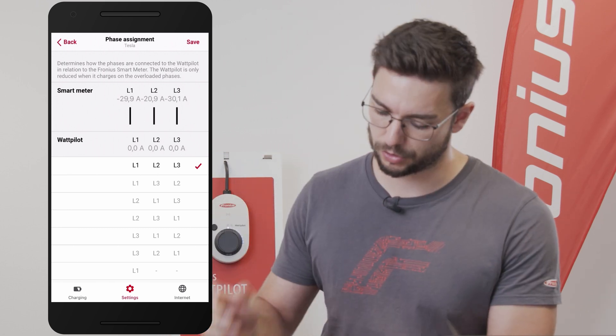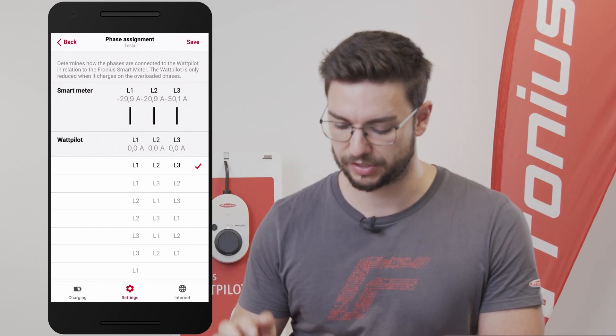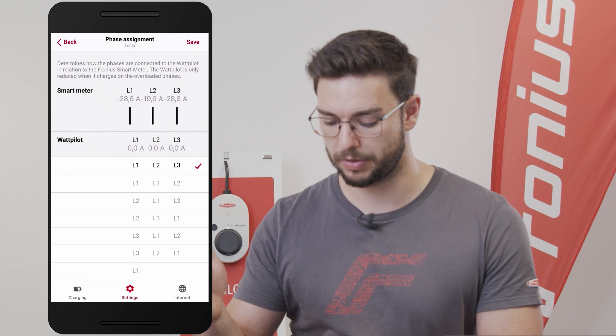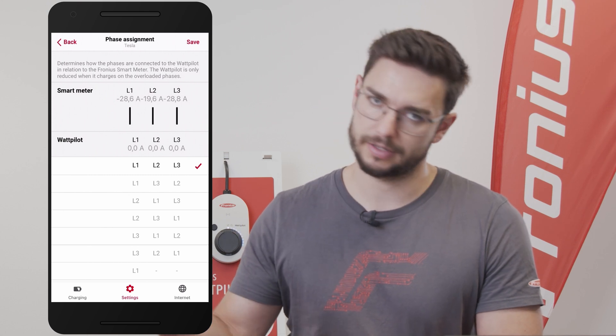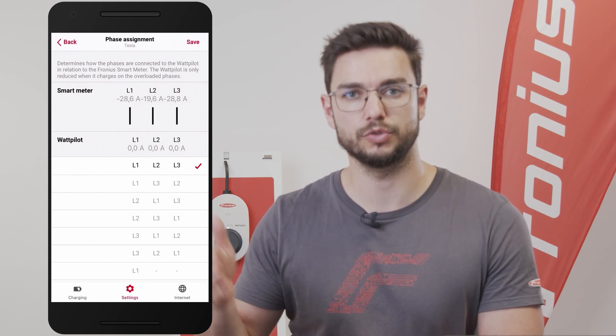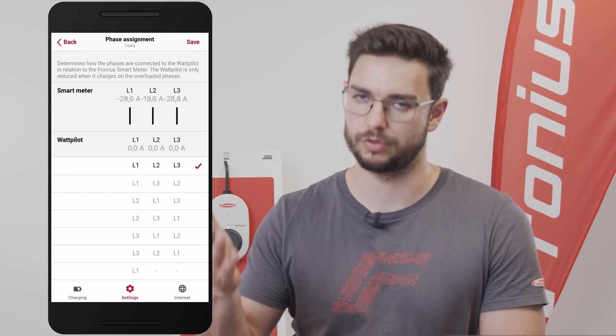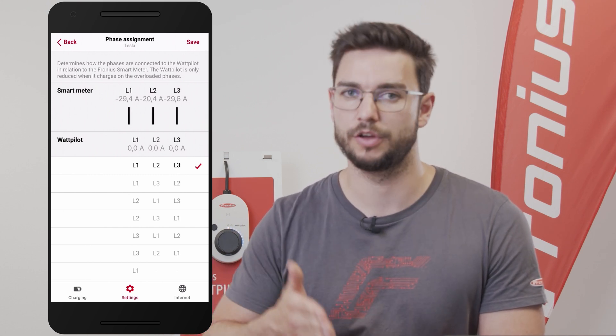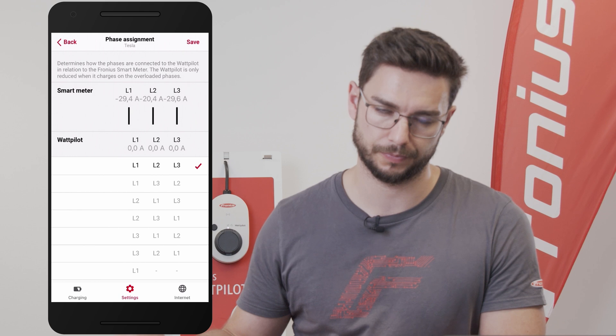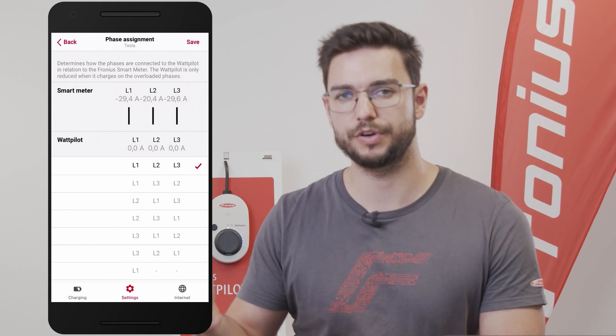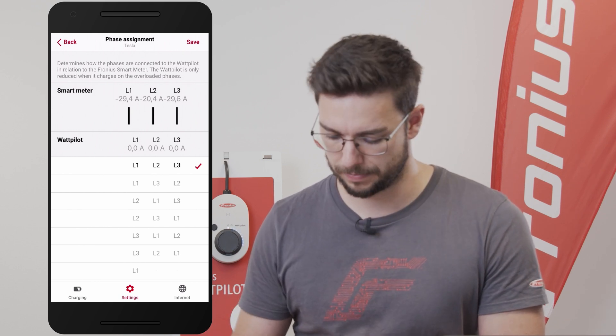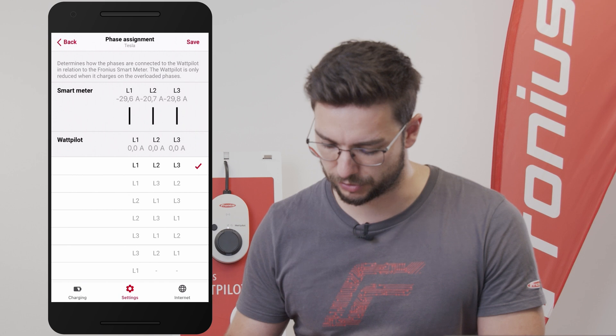If you use more than one Wattpilot, it makes sense to set the first one to assignment 1-2-3, the second to 2-1-3, and the third to 3-1-2, so all three phases are utilized for the single-phase Wattpilot connections.